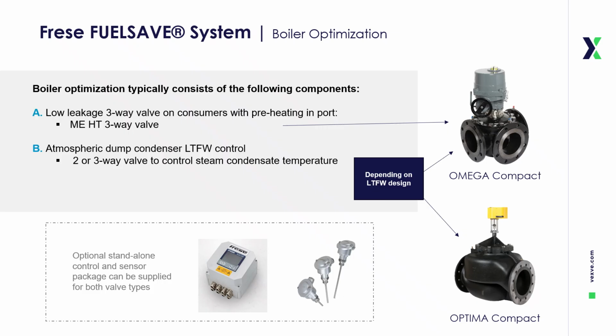The Optima Compact PICV provides automatic pressure-independent flow control with actuator integration, ensuring consistent thermal balance. The Omega Compact offers a robust three-way design with low leakage, compact footprint, and easy maintenance, ideal for dynamic boiler applications. Additionally, an optional standalone control and sensor package can be supplied for both valve types.